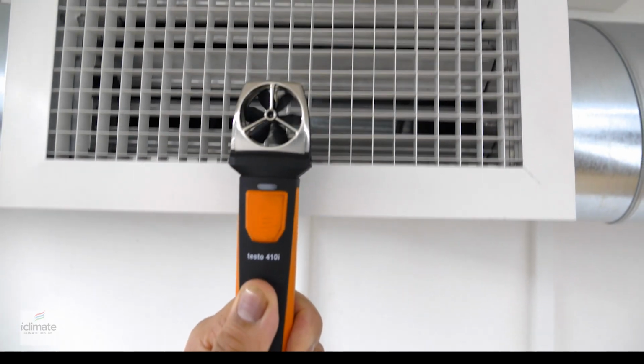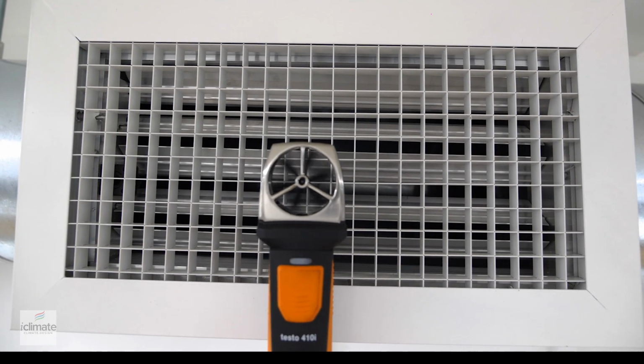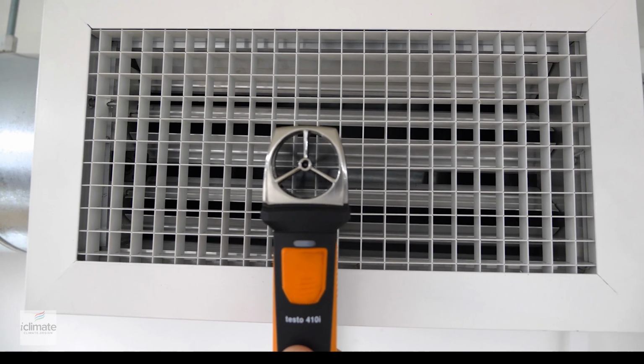So that means it's a heat recovery process. So the heat that we're generating from the space, generated by the radiators, gets transported through the air into the extract ductwork. It runs into the unit, and then there's a cross heat exchanger element. So we recover the heat that's produced from the building, cross it over into the fresh air from outside, and that gives it its name, the heat recovery ventilation system.